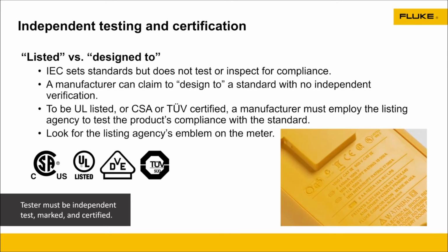When you talk about manufacturing of a meter, the standard says you need to do this, but sometimes the meter's not tested or inspected for that compliance. So look for markings on your meter that say UL listed or CSA listed. Even in other countries, you might see VDE and TUV. These are compliance standards where third-party organizations have taken a meter and tested it and made sure that it does meet that IEC 61010 rating that'll handle that.